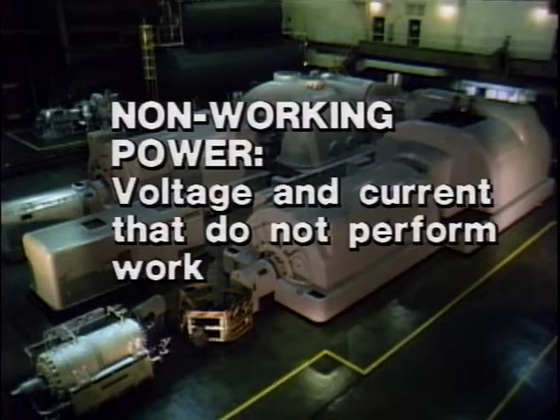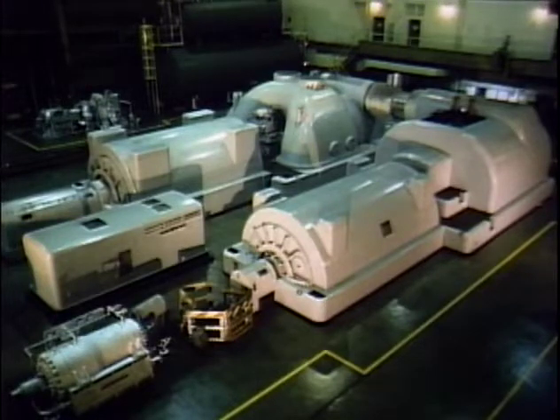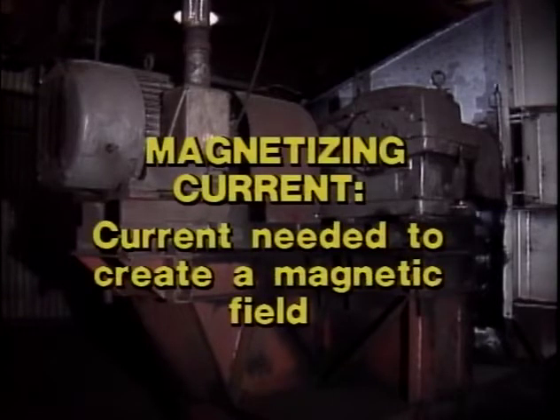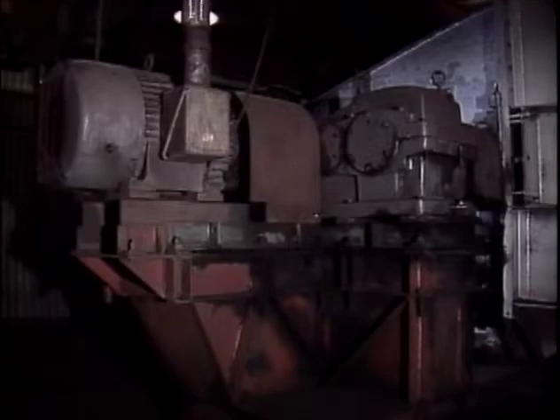Non-working power is voltage and current that do not perform work. Again, a key factor is what the current is used for. Some devices do not use all the current that they draw to perform useful work. For example, an induction motor needs a certain amount of current called magnetizing current to create a magnetic field in the motor. The magnetizing current does not perform work. Only after the magnetic field is created by non-working magnetizing current can working current operate the motor and perform work.